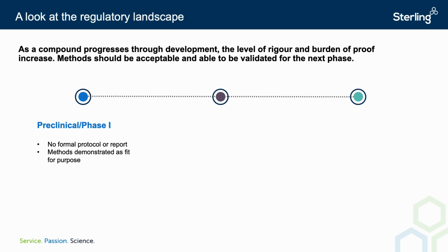The qualification of a test method can also be used in setting acceptance criteria for system suitability or for exposing weaknesses in a test method that can be easily modified before implementation or use testing a product. For example, during the qualification of a recent HPLC method, we realized that the components in a retention time marker solution were reacting with one another to form a new impurity. Using the data generated during qualification, we were able to update our test methods and release specifications with a modified retention time marker solution before product testing began.